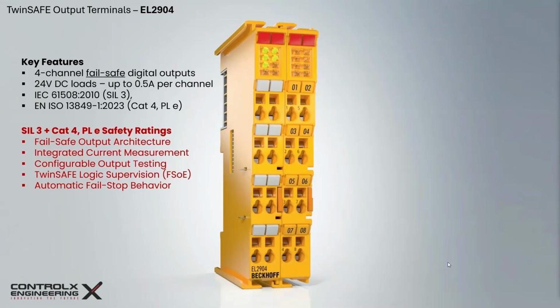If the terminal detects internal hardware faults, communication faults, parameter mismatches, or diagnostic failures, it automatically switches off its output, which is the fail-stop behavior. This ensures that no single fault can cause a dangerous output state. To meet the Category 4 PL e, the terminal is designed to tolerate any single fault, detect most faults immediately, and prevent accumulation of undetected faults. This terminal achieves this through redundant internal monitoring, continuous diagnostics, and safe shutdown on any anomaly.